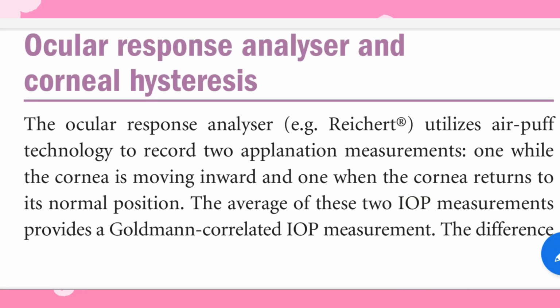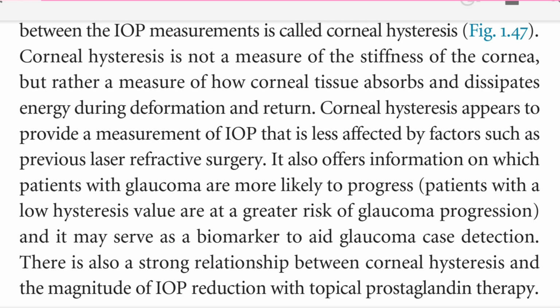Ocular response analyzer and corneal hysteresis. The ocular response analyzer, for example Reichert, utilizes air puff technology to record 2 applanation measurements, one while the cornea is moving inward and one when the cornea returns to its normal position. The average of these 2 IOP measurements provides a Goldmann correlated IOP measurement. The difference between the IOP measurements is called corneal hysteresis, figure 1.47.